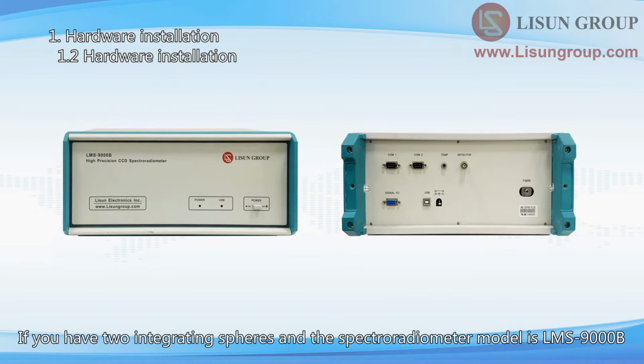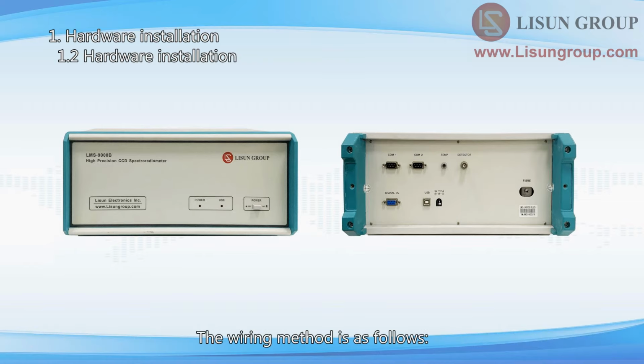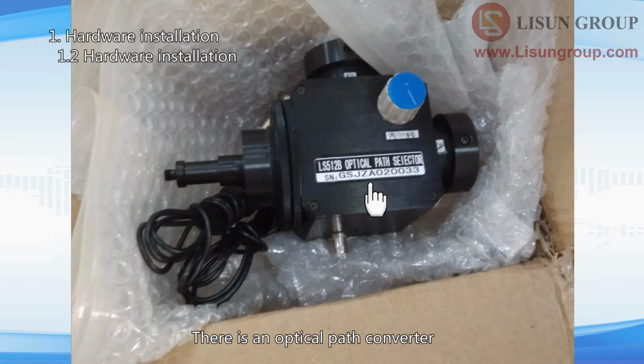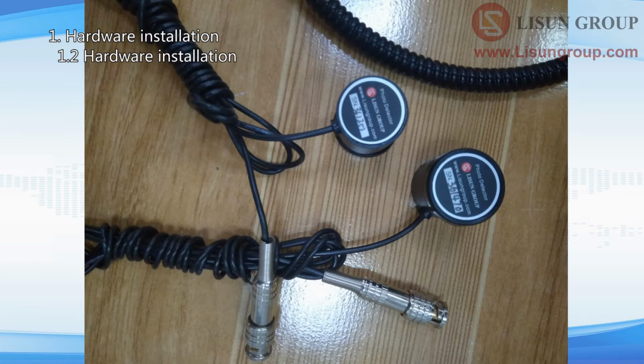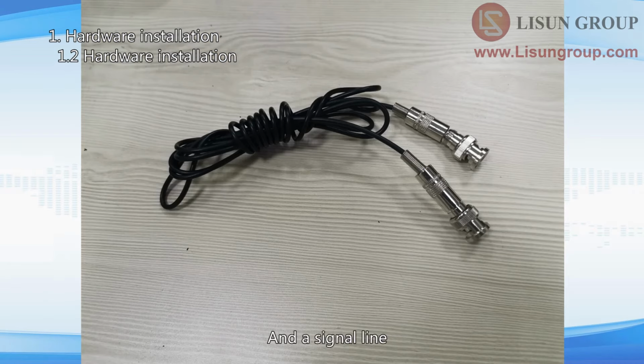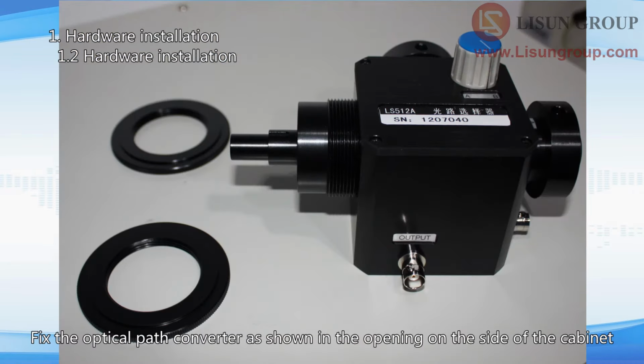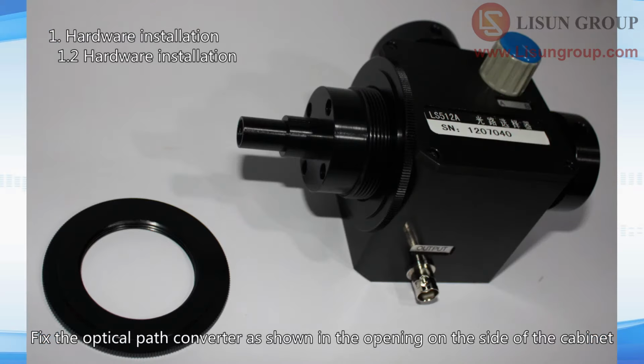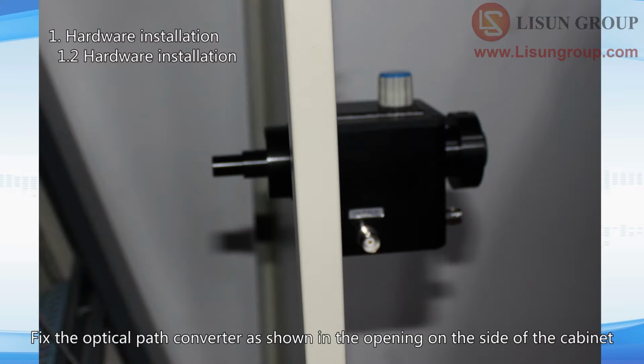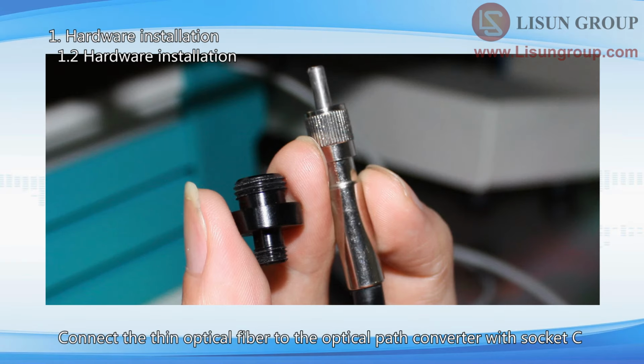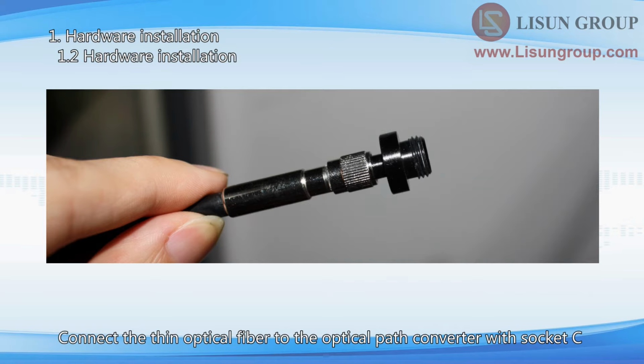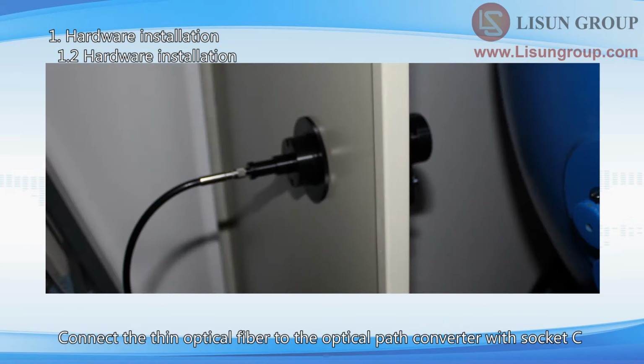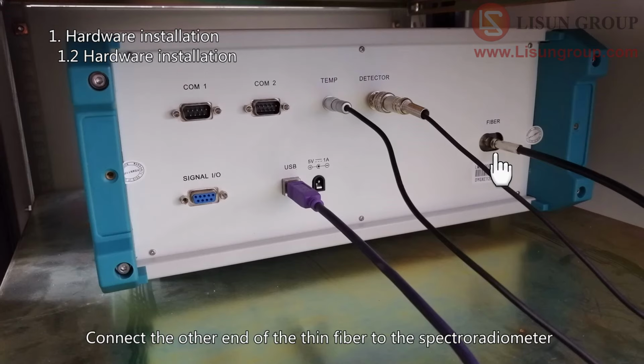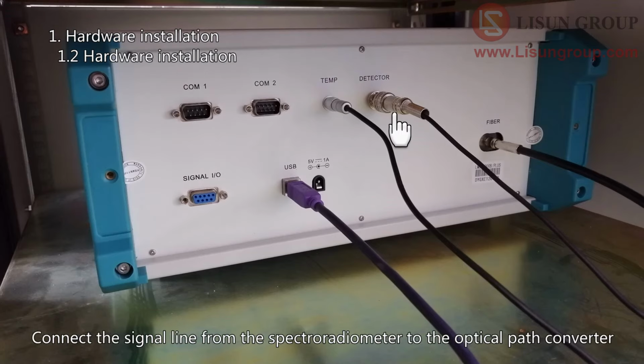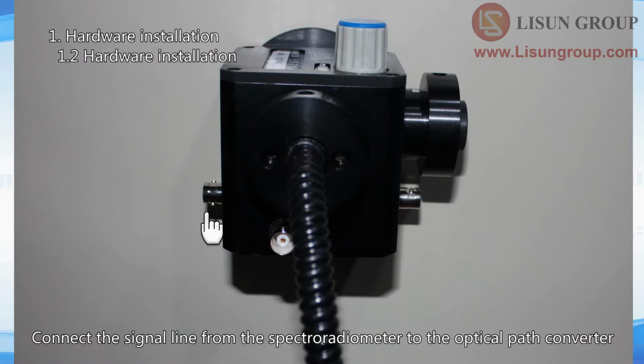If you have two integrating spheres and the spectroradiometer model is LMS-9000B, the wiring method is as follows. There is an optical path converter, two more thick optical fibers, two detectors, and a signal line. Fix the optical path converter as shown in the opening on the side of the cabinet. Connect the thin optical fiber to the optical path converter with socket C. Connect the other end of the thin fiber to the spectroradiometer. Connect the signal line from the spectroradiometer to the optical path converter.